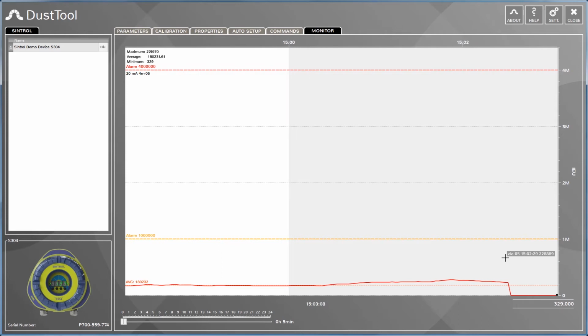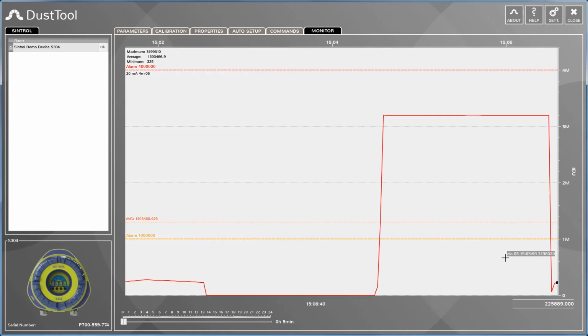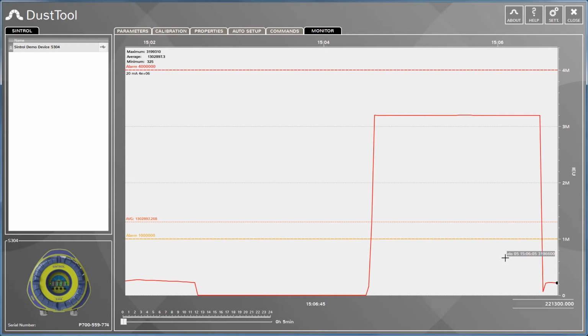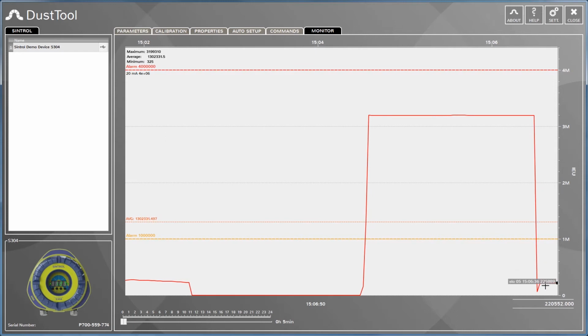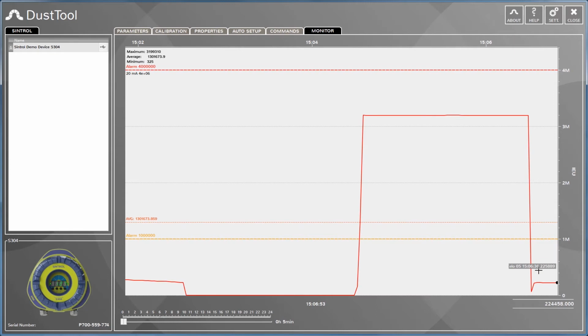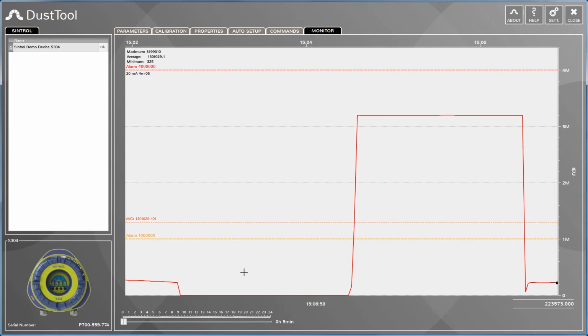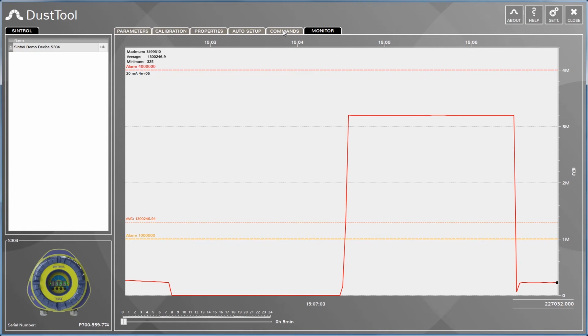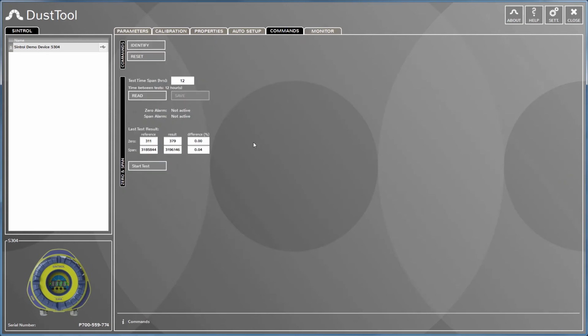We will speed up that a little bit by cutting the video. Alright, now the zero and span check is finalized and your instrument goes back into measurement mode. Note, also the relay configuration goes into maintenance mode during the period of zero and span. You can go back to the Commands tab and we can see that the test has finalized and the differences have been noted.